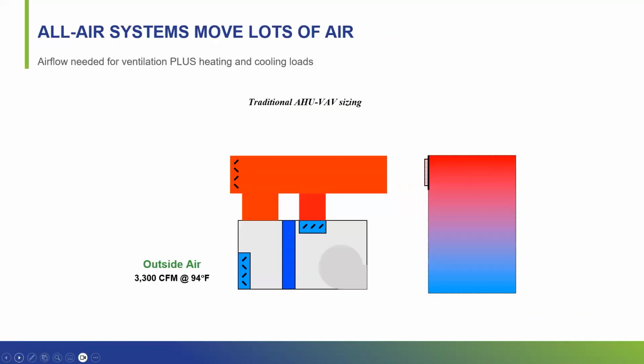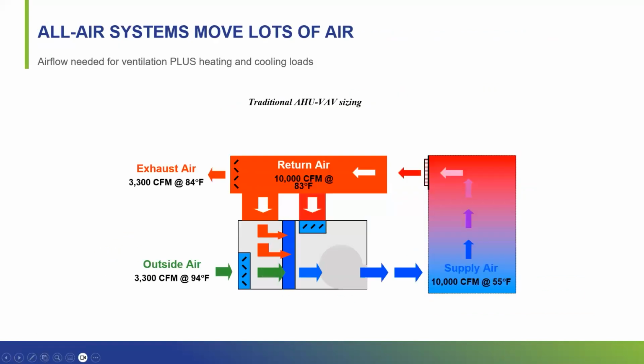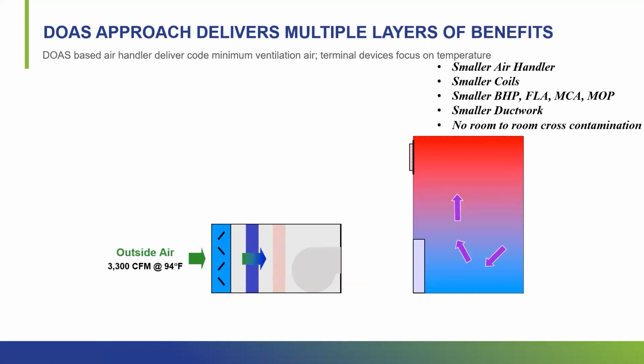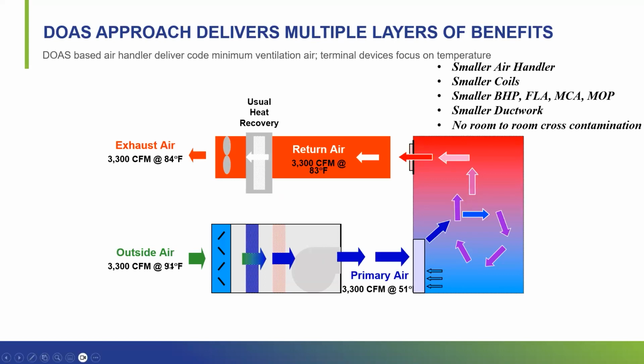And then if you look at the air handler design, an all-air design typically is much larger and needs to deliver cooler air to heat and cool the space. And then you have a large portion of return air that has to be handled. So the ductwork is large as well. And then you have to return that air back to the space, deal with it, and then circulate it again back to the space.